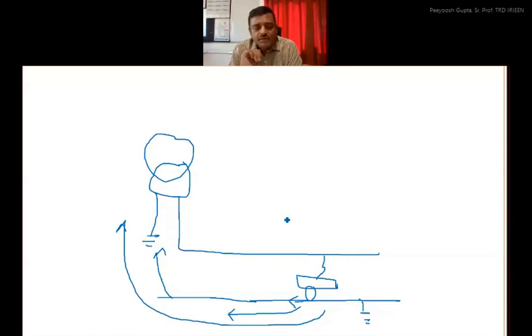What happens if current doesn't flow? Suppose there is a mast but we have not connected the bond, and live 25 kV OHE is touching the mast - what will happen? There will be high resistance, high impedance, and because of that the current will be very low, and it's likely our relays won't operate. So what we have done is provide a delta current, delta I relay, which takes care of such situations.